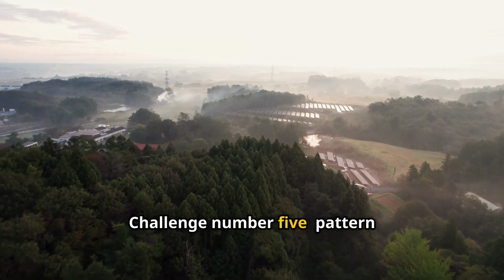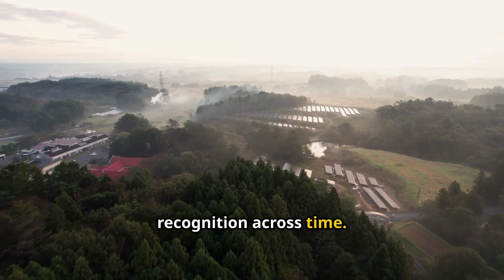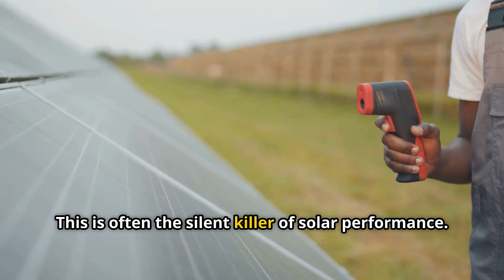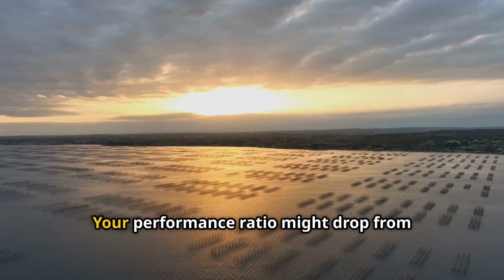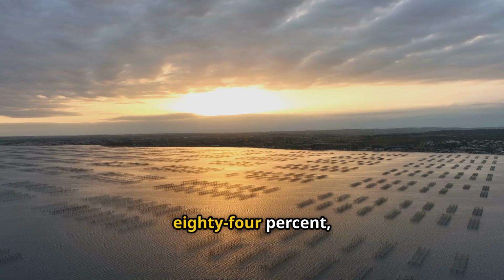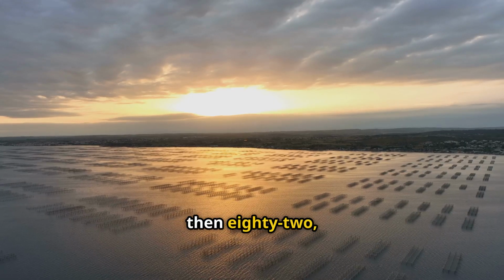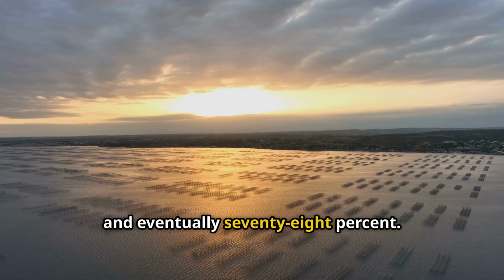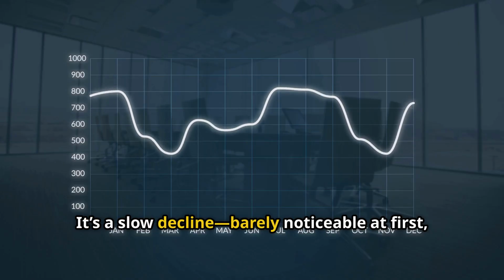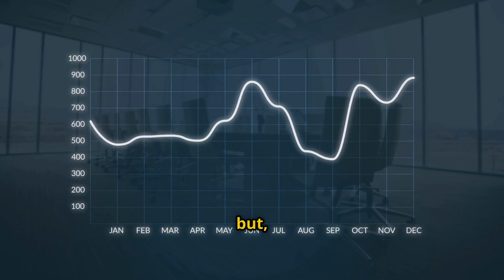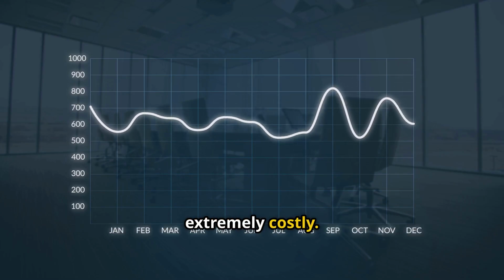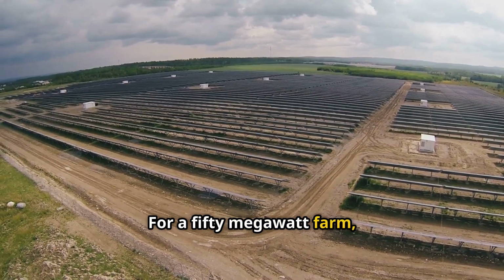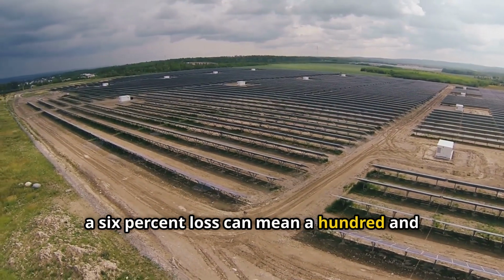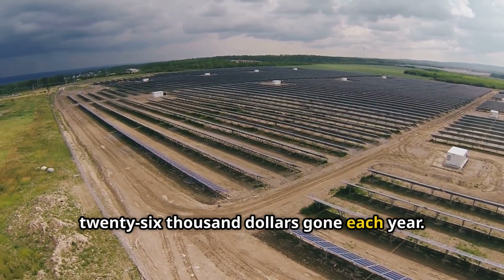Challenge number 5, pattern recognition across time. This is often the silent killer of solar performance. Your performance ratio might drop from 84% to 83, then 82, 80, and eventually 78%. It's a slow decline, barely noticeable at first, but honestly, extremely costly. For a 50-megawatt farm, a 6% loss can mean twenty-six thousand dollars gone each year.